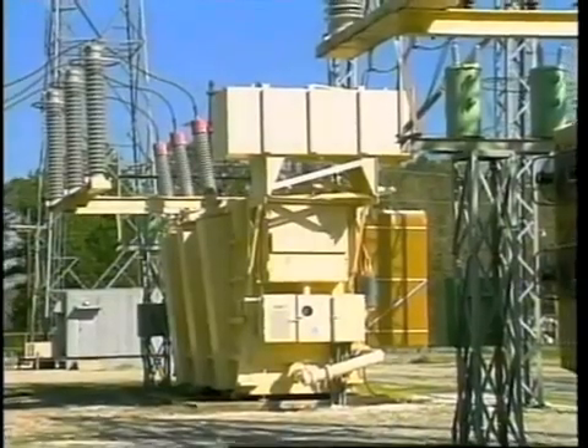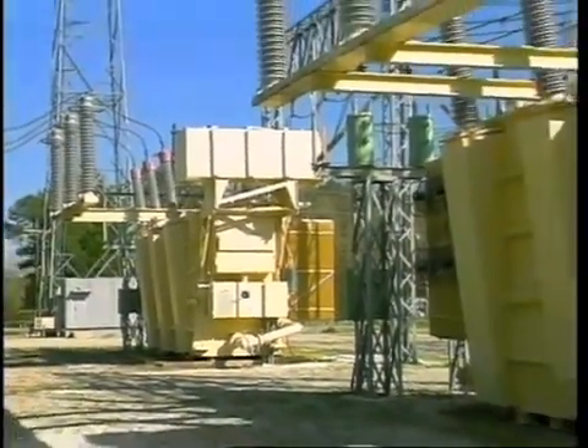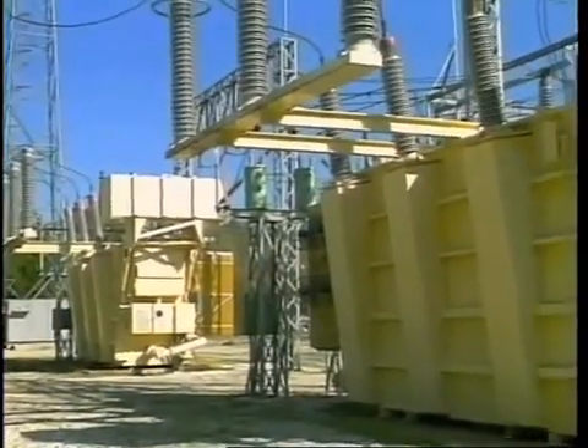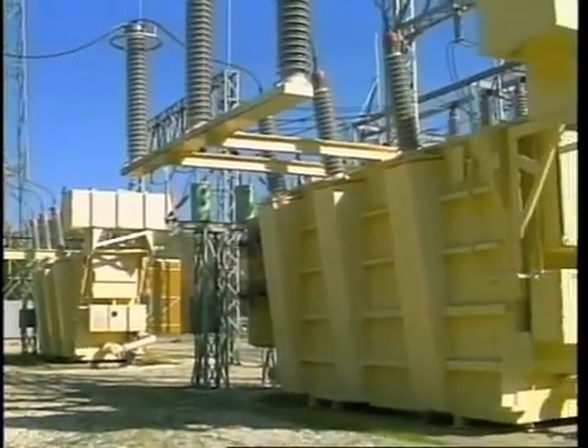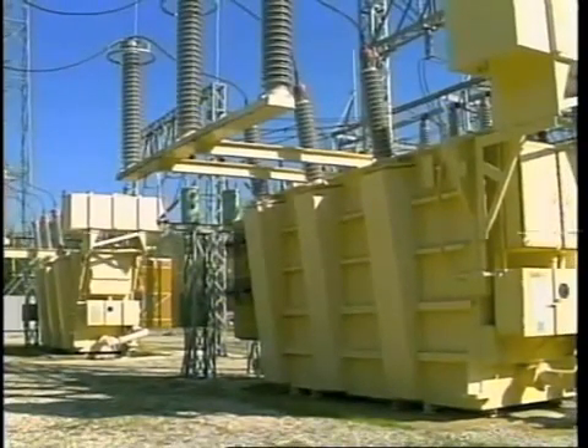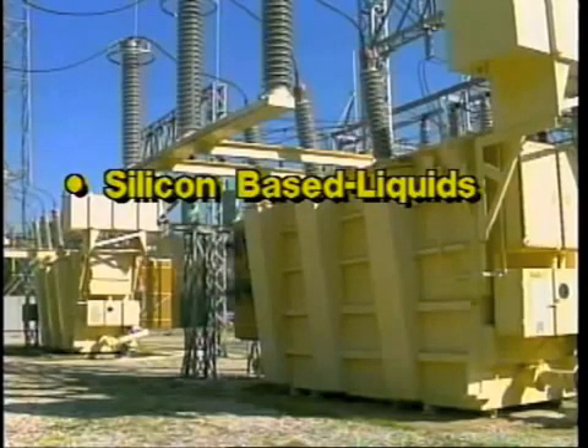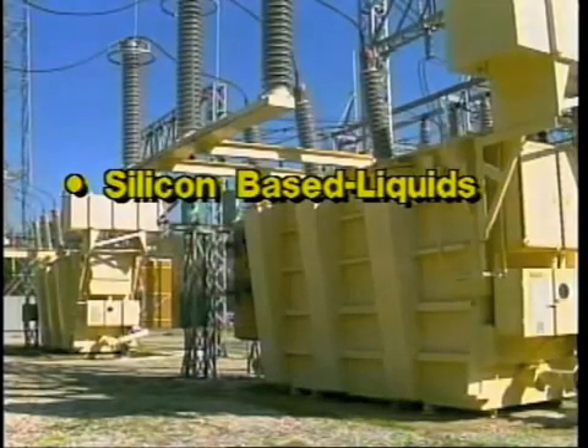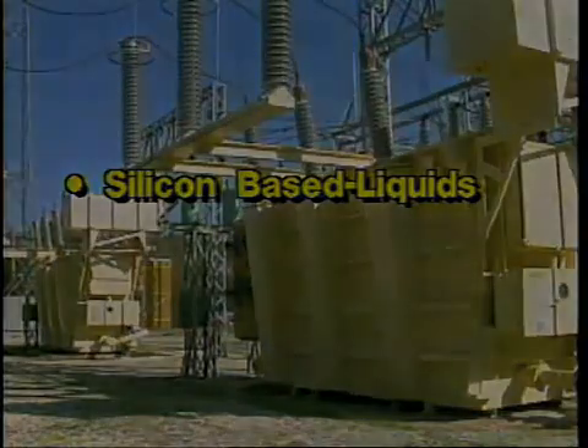Current losses in the steel core and the conductor coils produce heat. Some type of cooling device must be incorporated into the design of the transformer to dissipate this heat. Commercial transformers are cooled by immersion in a liquid or by air cooling. Liquid-cooled power transformers use a variety of materials for cooling. Silicon-based liquids are one type of material used.